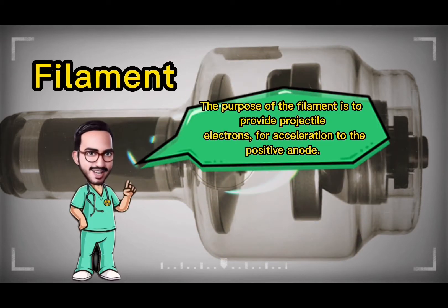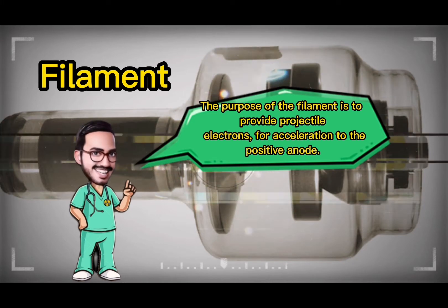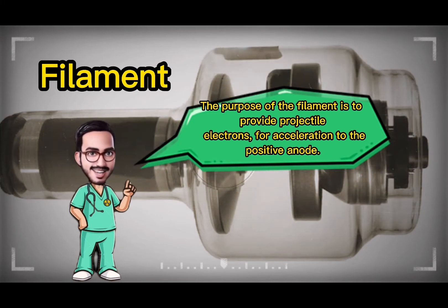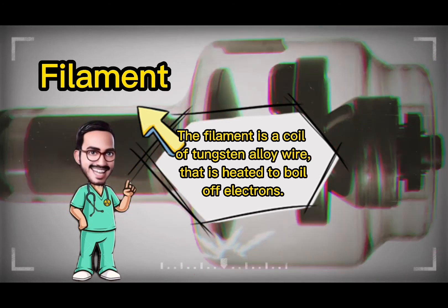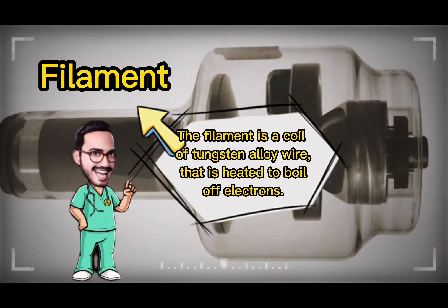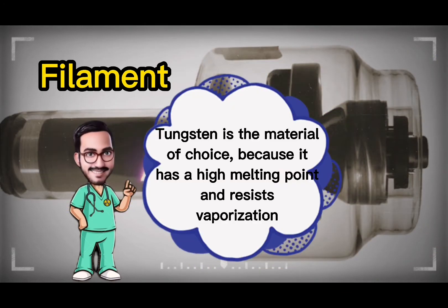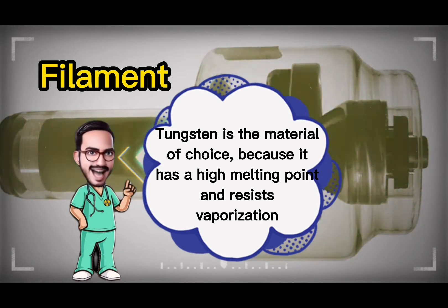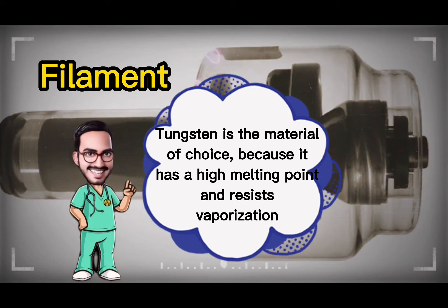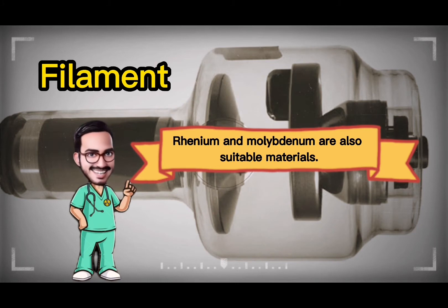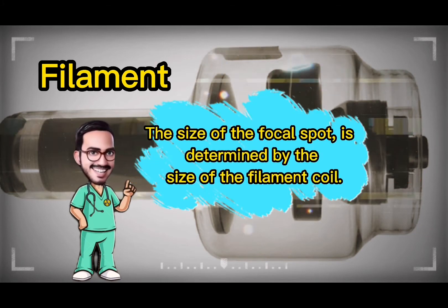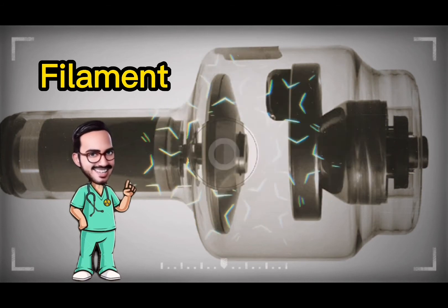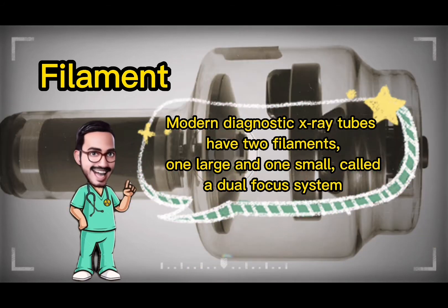The purpose of the filament is to provide projectile electrons for acceleration to the positive anode. The filament is a coil of tungsten alloy wire that is heated to boil off electrons. Tungsten is the material of choice because it has a high melting point and resists vaporization. Rhenium and molybdenum are also suitable materials. The size of the focal spot is determined by the size of the filament coil. Modern diagnostic x-ray tubes have two filaments — one large and one small — called a dual focus system.